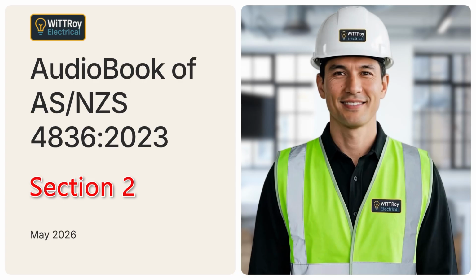Other risk factors include damp situations, heat, cold, vibration, noise, working at height, falling objects, pressure to restore electricity supply, instability of the work area, conductors or equipment under tension, nearby machinery, below ground work, toxic or corrosive materials, radiation, asbestos, PCB materials, conductive dust, poor work practices, working alone, equipment design, and the position of exposed energized conductors or live conductive parts. This clause reminds us that electrical safety is affected by the whole job situation.